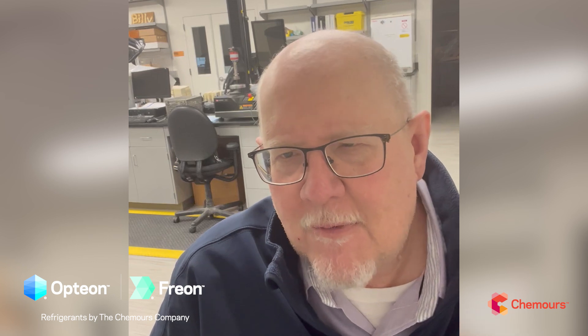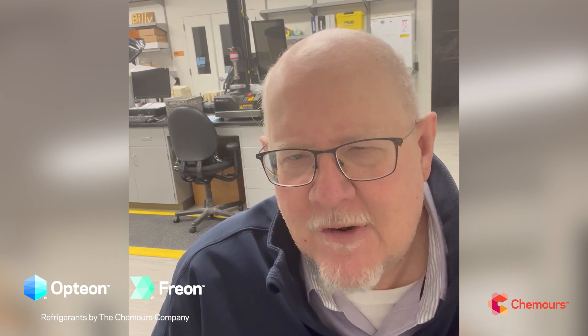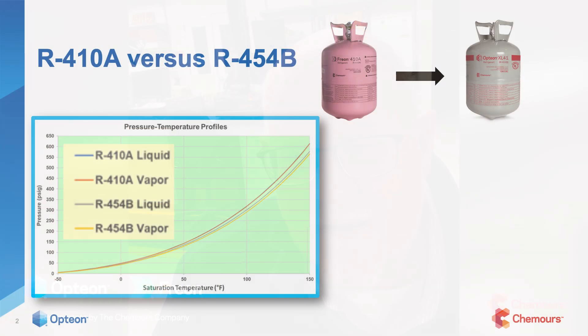I want to throw the pressure-temperature curves up here — that's the heart of what we do in the HVACR industry, pressure-temperature manipulation. You can see how close they are: both the liquid and vapor pressures for 410A and 454B are pretty much right on top of each other over the whole applicable range.